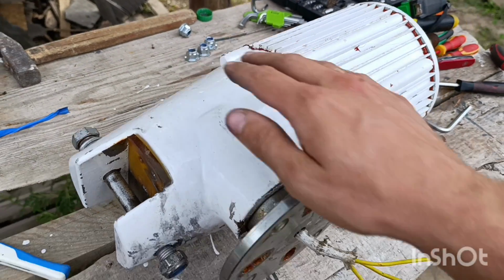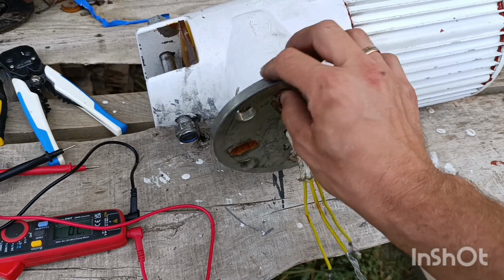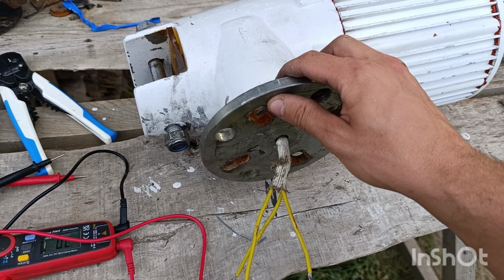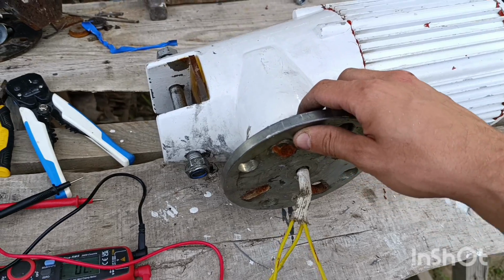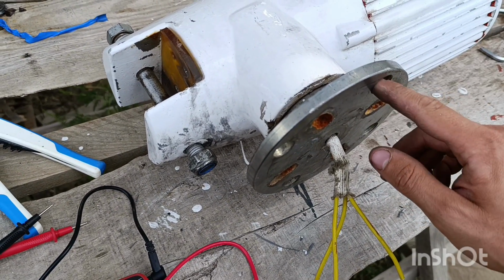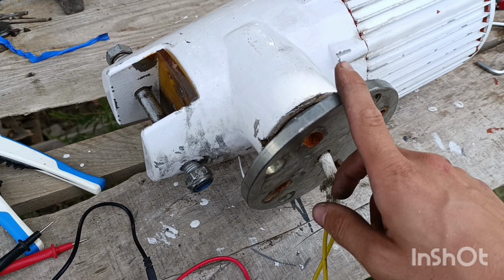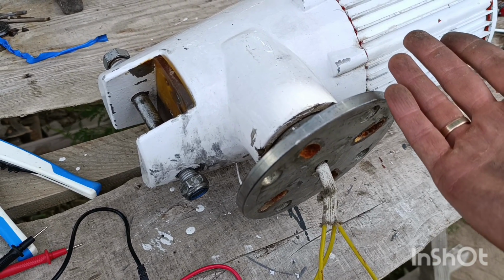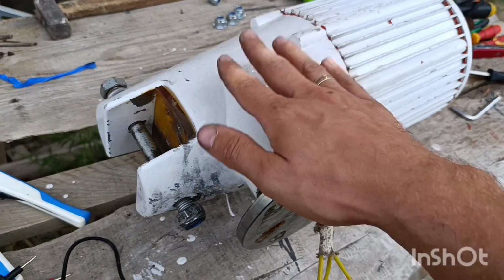I'm just not sure how this carbon brush went off. It definitely got stuck, as you have clearly seen, and it started burning because it was giving an arc to the contact, to the slip contact. However, it was working until the very last day. It's been laying down for over a month now, just waiting for the place.